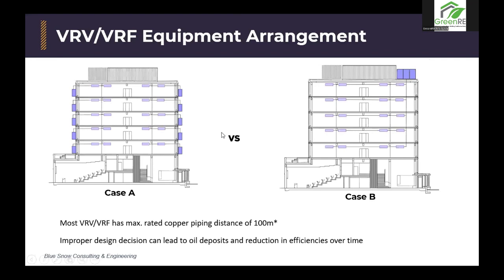And to size these copper pipes, you will need to use those suppliers' proprietary software. For example, if you're going to use a Daikin unit, you need to use their VRV system sizing software. For example, VRV Xpress is for Daikin. Hi-Tech, I think, was Hitachi's one, because you will need to actually equate the length of the copper pipes. And if you have any bends, there's an equation and calculation on what you need to do to calculate the equivalent length for a 90-degree bend or a 45-degree bend. And only then do you size each copper pipe, how long and how thick those need to be going to the indoor system.